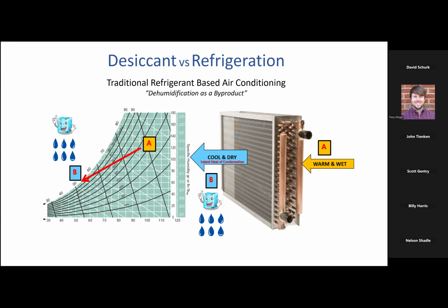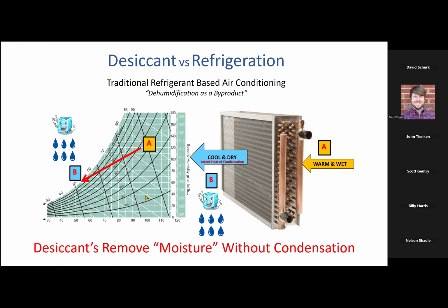And that's a problem. So in situations like that, where I have low relative humidity requirements in the space, and I cannot achieve enough moisture removal with a cold coil surface, I have to use something that will remove moisture from the air without condensation, something that will hold moisture as a molecule, never letting it get wet, never letting it condense, so that I can pull the moisture out of the air, but I don't have issues with condensate freezing. And you know what? Silica gel. Desiccant dehumidification is a perfect way to accomplish that. And we'll talk more about that in a minute or two.